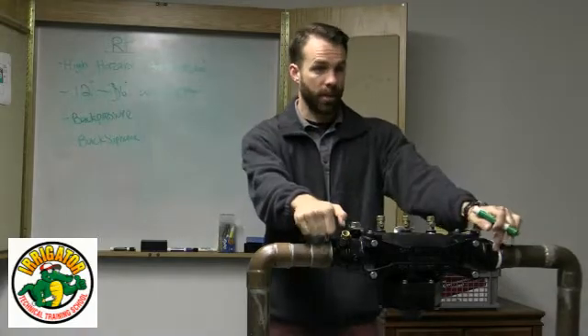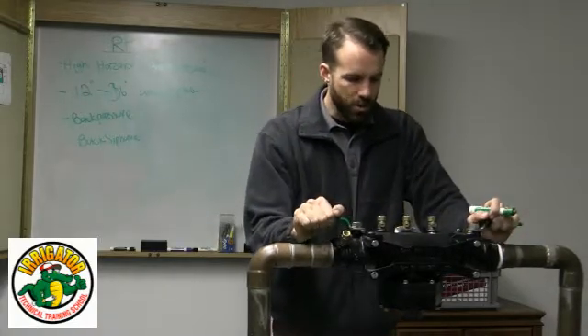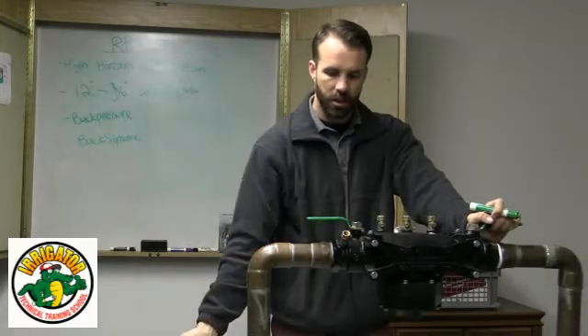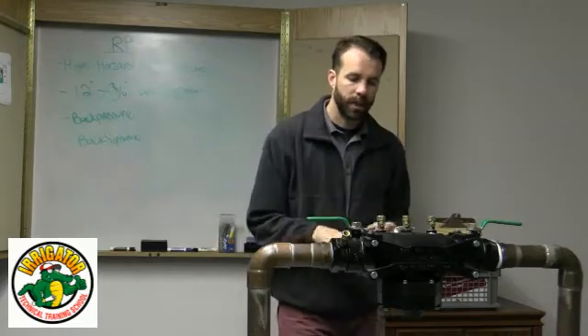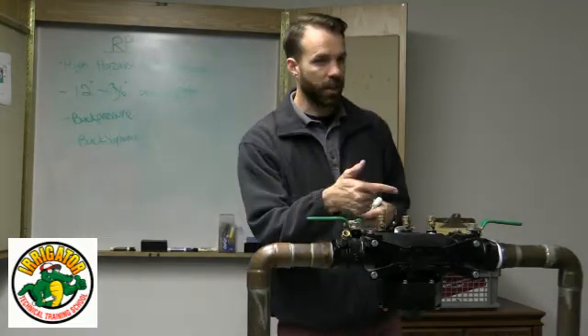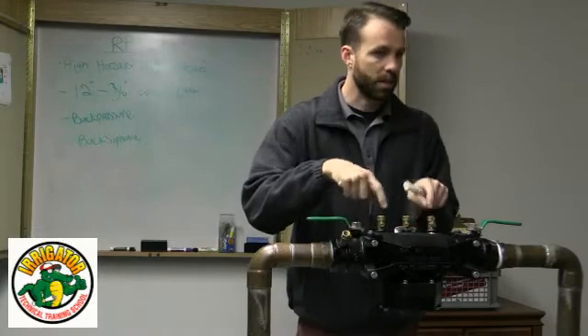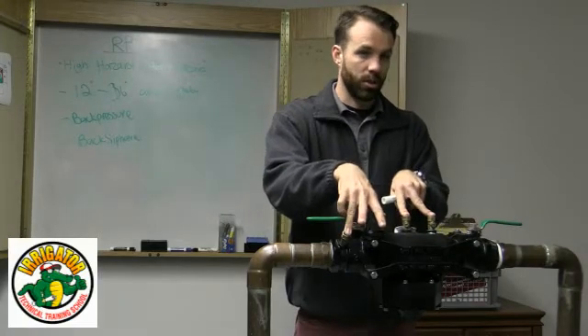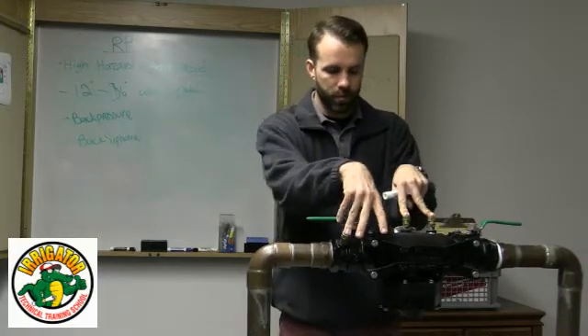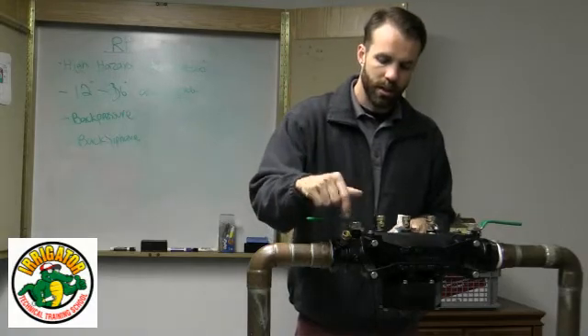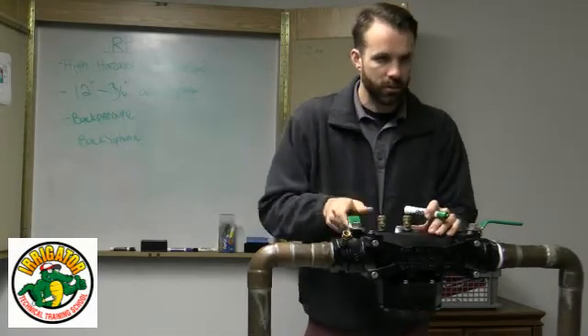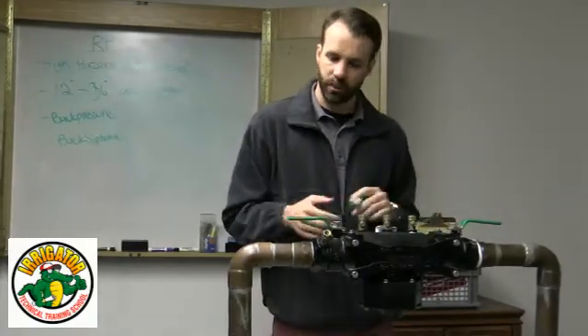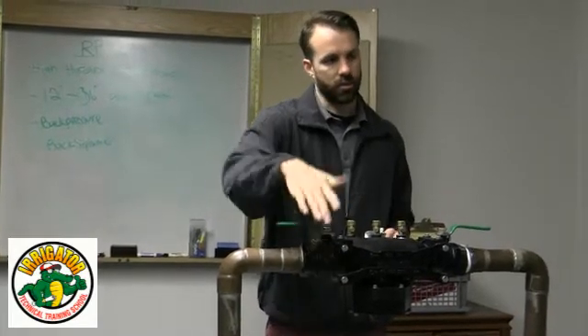Okay, so since I have this in front of me, which way is the water going? This way. We see there's an arrow here. But we know the meter here. So just to clarify some of the components names, which will help us identify the way the water goes. These are the test cocks. There's four of them: one, two, three, four. These are only here so I can certify it and test it. The number one is always on the number one shut off valve. So shut off valve one and two. If you don't see the arrow, which can happen, people paint or something like that, you know, the water is going to go this way because this is the first one.